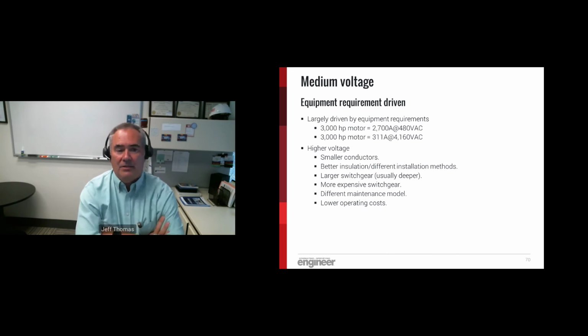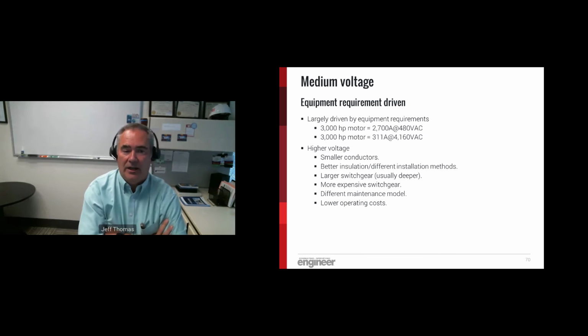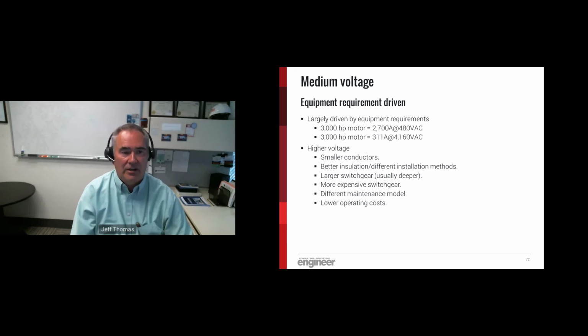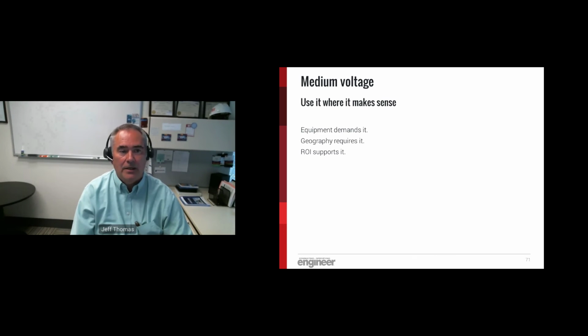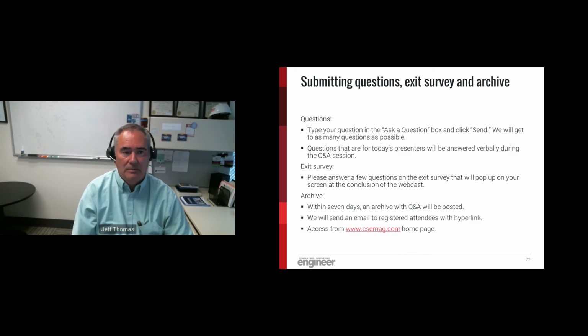And it's a different maintenance model. If you're an existing facility that's got folks that can maintain 480 volt equipment, if you throw 4160 into the mix, it's very different for them. So you've got to keep that in mind. So basically, use it where it makes sense, and where the ROI and the geography support it. And with that, I will give it back to our lead presenter, Amara.